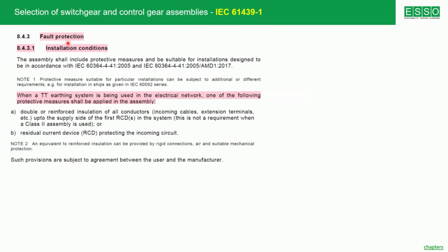Now, for a switchgear and control gear assembly, you see here fault protection. When a TT earthing system is being used in the electrical network, one of the following protective measures shall be applied in the assembly. That means if your installation is a TT system, then you must apply this kind of method in your panel board. For example, double or reinforced insulation of all conductors such as incoming cables, extension terminals, etc., up to the supply side of the first RCD in the system, or a residual current device protecting the incoming circuit. So if you are buying a panel board and going to use it in a TT system, then you have to take care of the protective device which you are using.